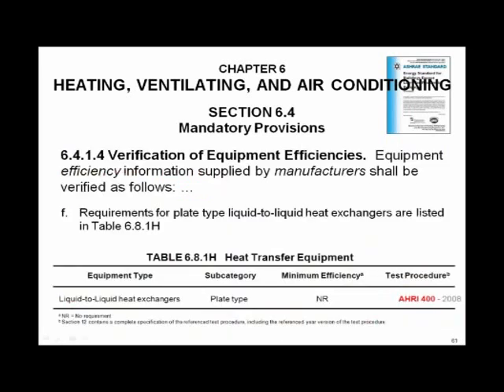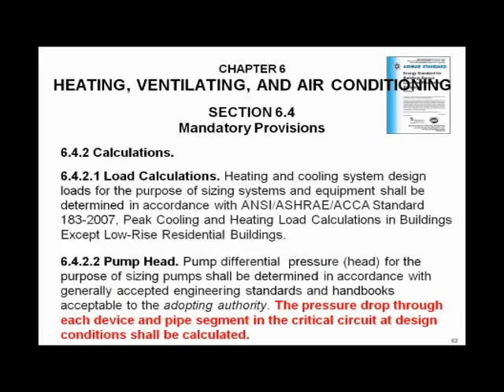So what are some other things? Simple little thing, but it's really something very important to the industry. You need to change your specifications today so that every plate heat exchanger that you use is AHRI certified. There's nothing proprietary about it. It just stops a lot of issues, and it's pretty much in the code. DOE's asking for it, 90.1's asking for it. So right now, if you don't need anything else, go to your specifications and put a line in your guide that all plates shall be AHRI certified. Simple as that. You do it for chillers, you do it for cooling coils. Why wouldn't you do it for heat exchangers?